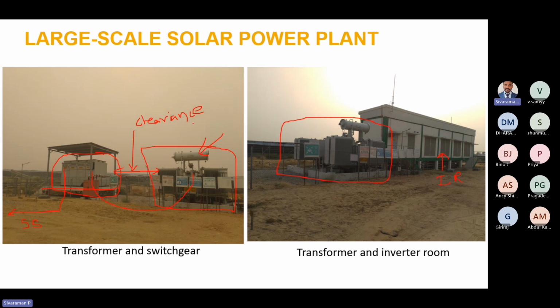So this is a mandatory requirement for our India. Whenever there is an oil-based transformer, we should not keep other equipments very nearby. We have to maintain a certain distance as a clearance. Suppose we need to place two equipments very nearby due to land availability constraint, in that case we have to provide the firewall between the equipments.